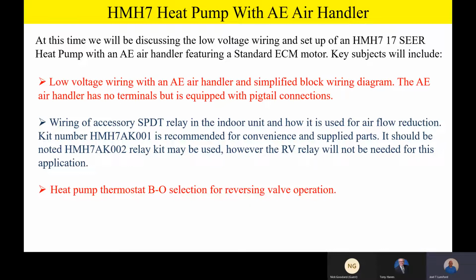Now, it's exactly opposite of the rest of our Champion product. We energize on our other heat pump products in the O terminal for cooling mode, but this HMH7, we energize the B terminal for the heating mode. It's not bad, it's just different. We need to keep that in perspective and make sure that our heat pump thermostat has a BO selection, so we can select that B terminal for heating operation.